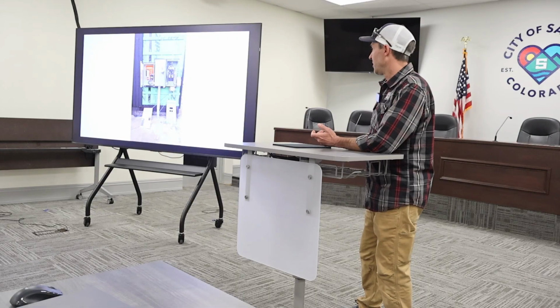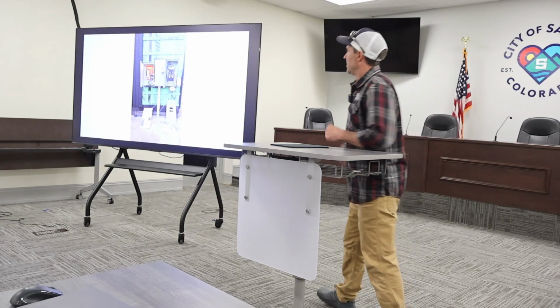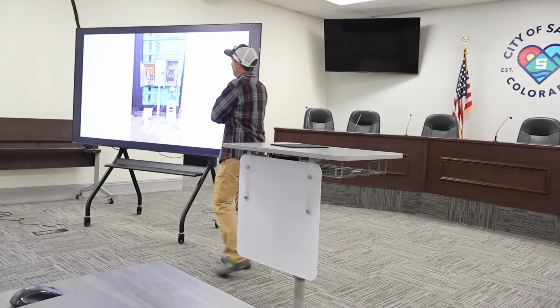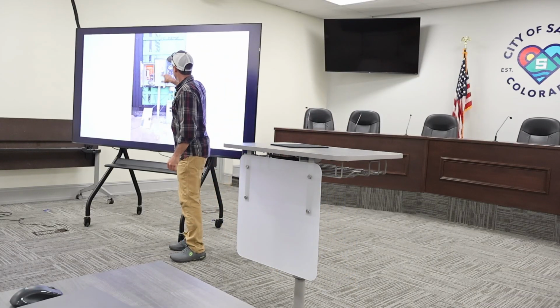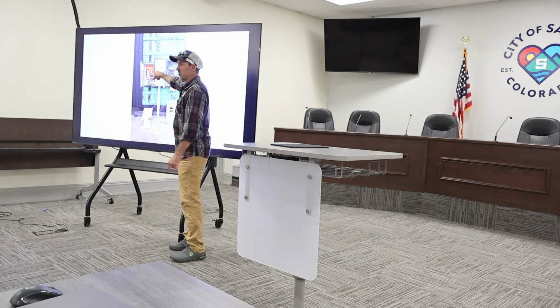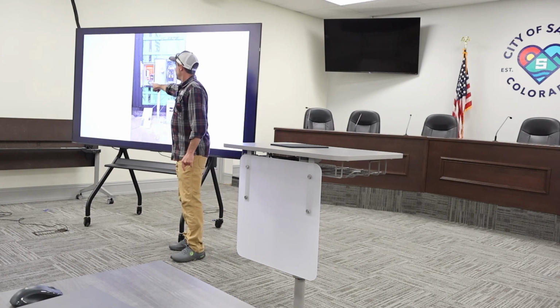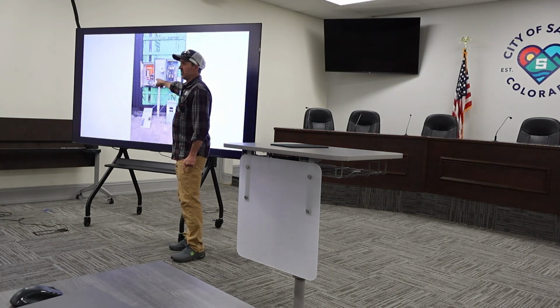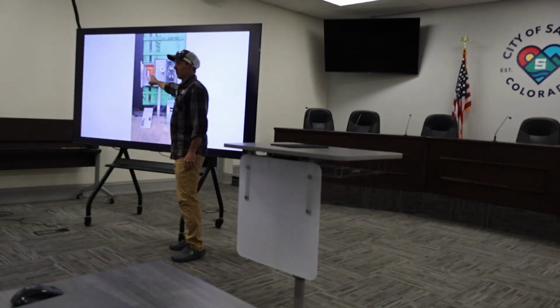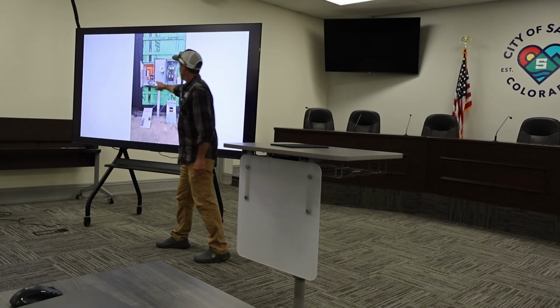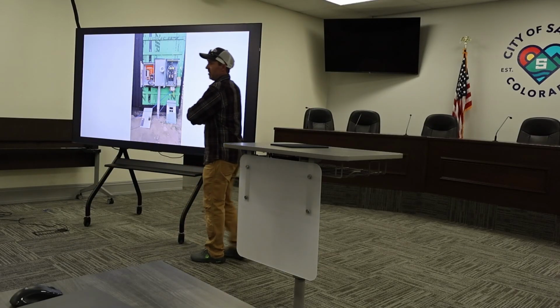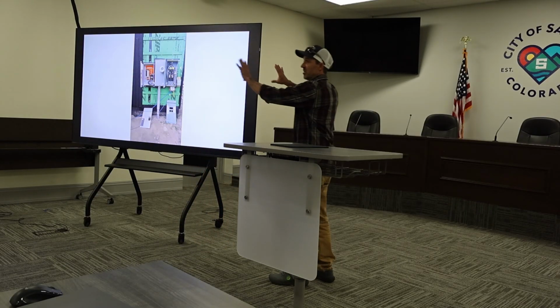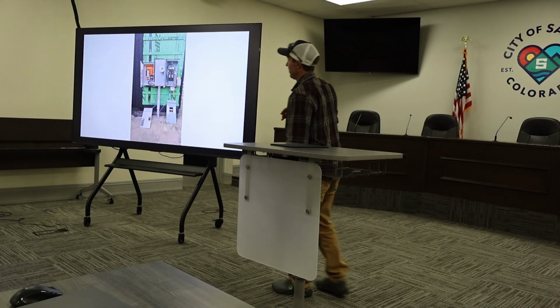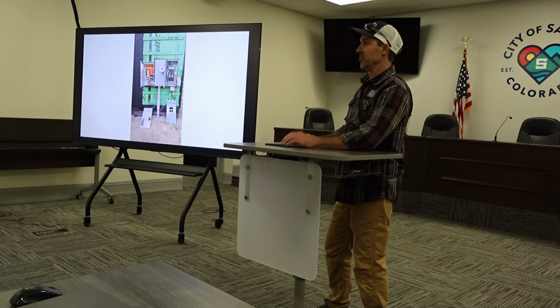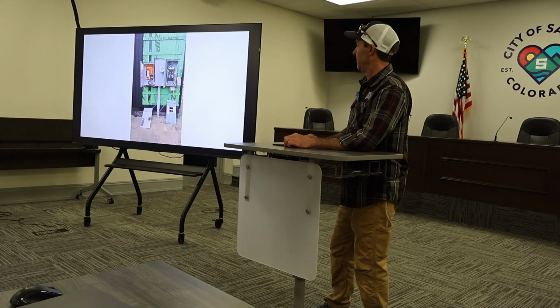Same situation. Here's a 320 amp service. What I was trying to display with this is, you know, most of these bigger services have two panels or two disconnects before they enter the building. A lot of these transfer switches are service-rated disconnects, so this serves as the disconnect for the house. This one is a disconnect going to one panel, and this serves as the disconnect going to the other. That comes in real handy, so we don't have to have two disconnects in a transfer switch. But once again, new construction, we're able to do that up front, and it turned out to be pretty clean.